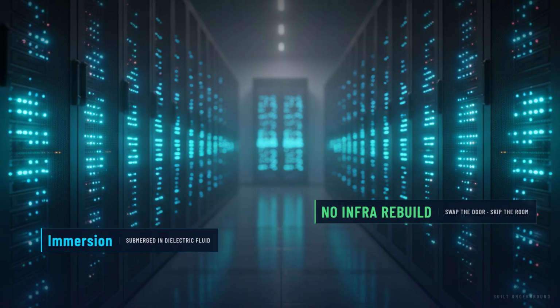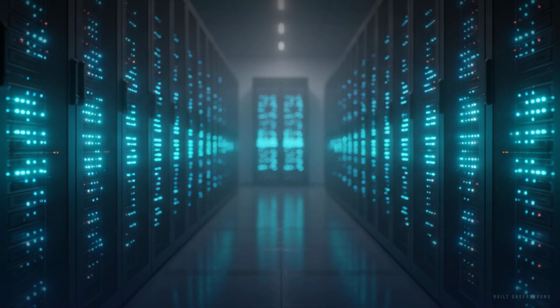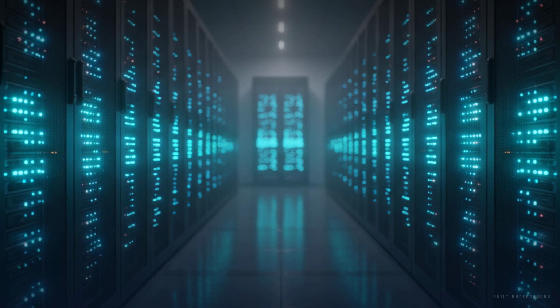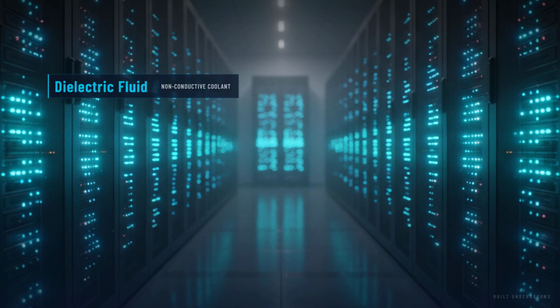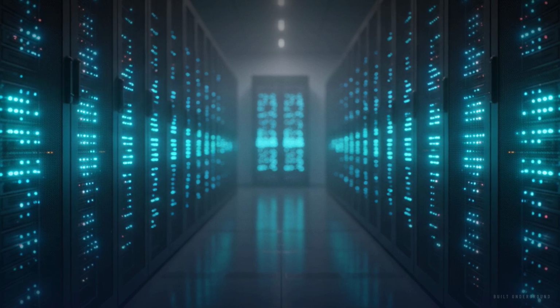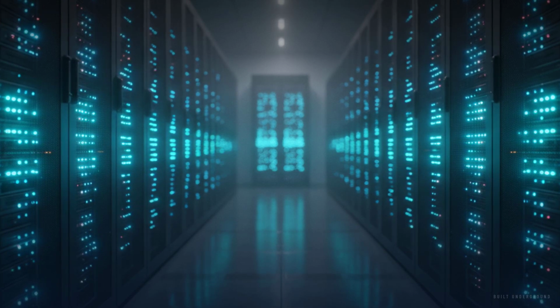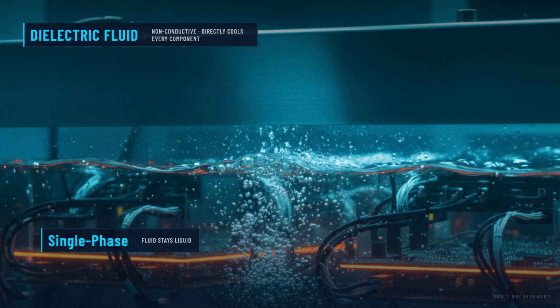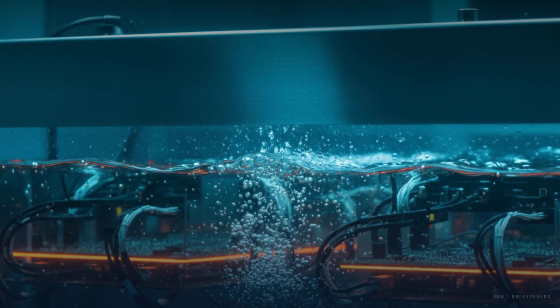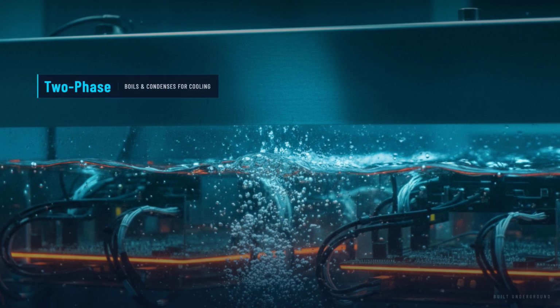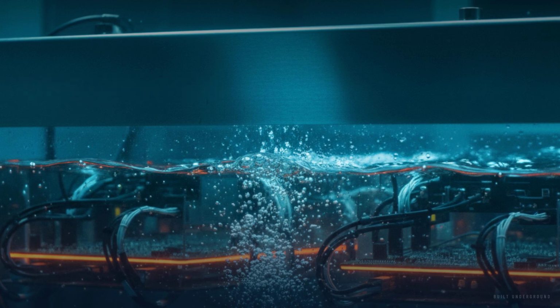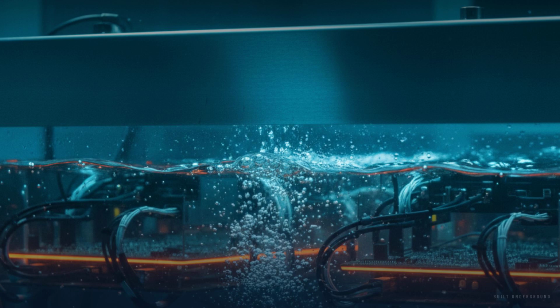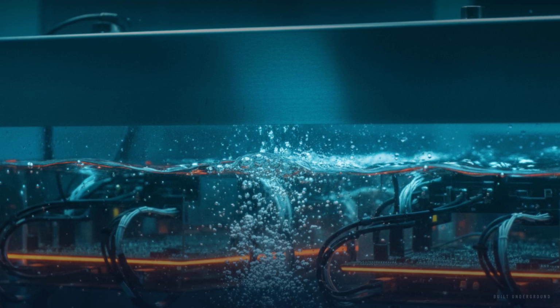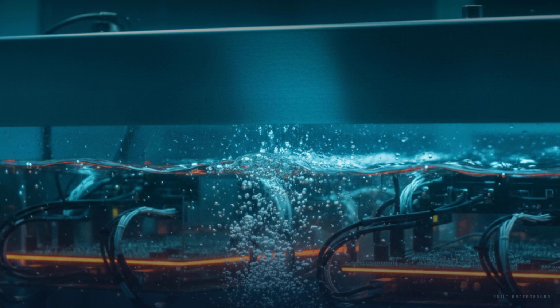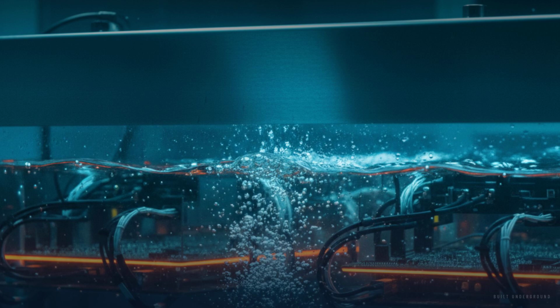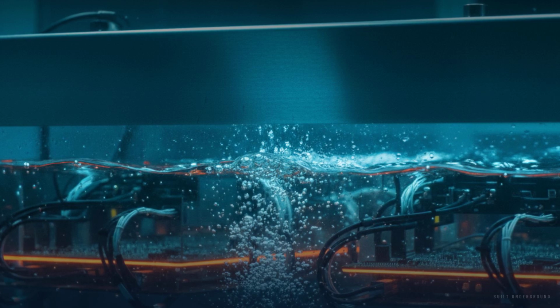Immersion cooling is the most radical approach. The entire server, bare board with no casing, is submerged in a tank of dielectric fluid, a non-conductive liquid that absorbs heat directly from every component simultaneously. Single-phase immersion uses a fluid that stays liquid throughout the process. Two-phase immersion uses a fluid that boils at a low temperature, turning to vapor as it absorbs heat, then condensing back to liquid in a condenser above the tank. Two-phase is more efficient, but significantly more complex and expensive.